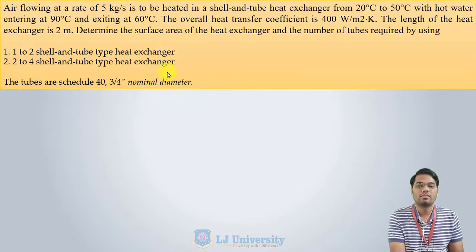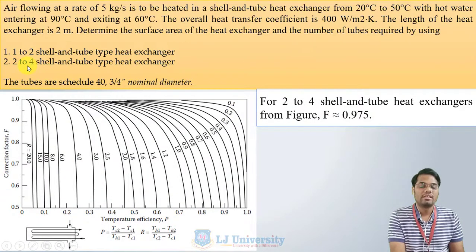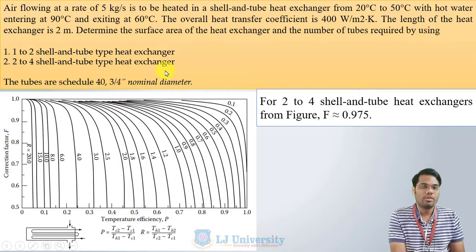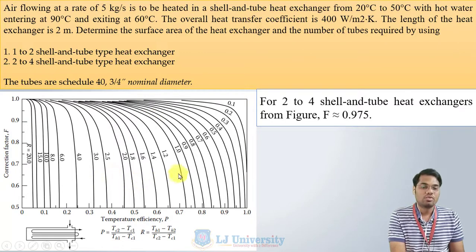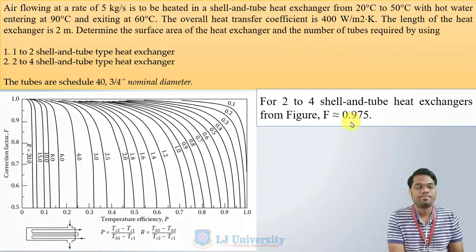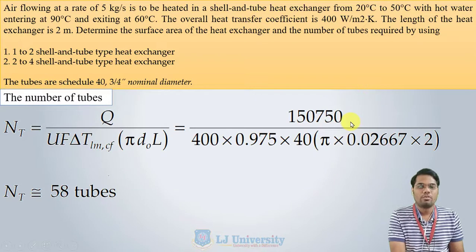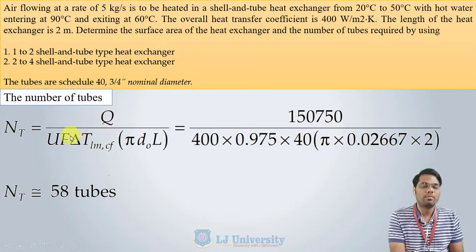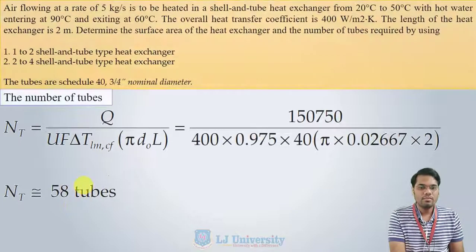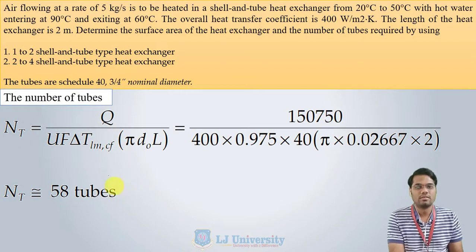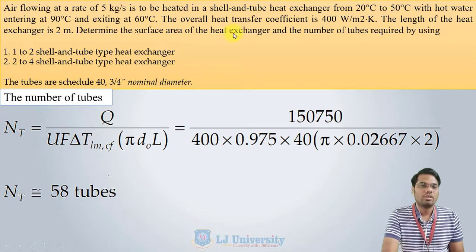For Case 2 — the 2-4 shell and tube heat exchanger — Q, P, and R remain the same, but a different graph is used. According to the values of P and R, the correction factor F is approximately 0.97. Using the same equation, the number of tubes required is approximately 58 tubes. These are the results for both configurations.